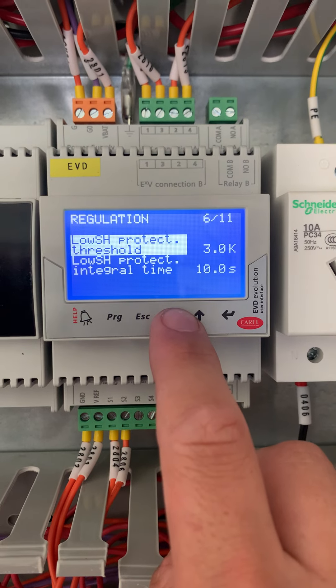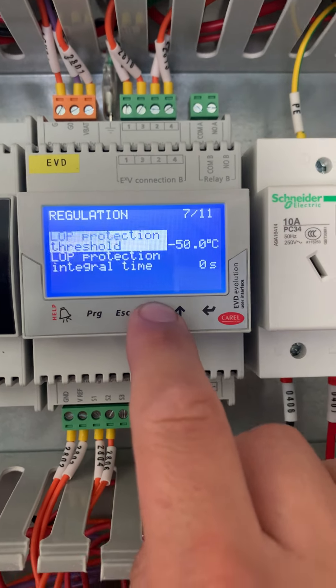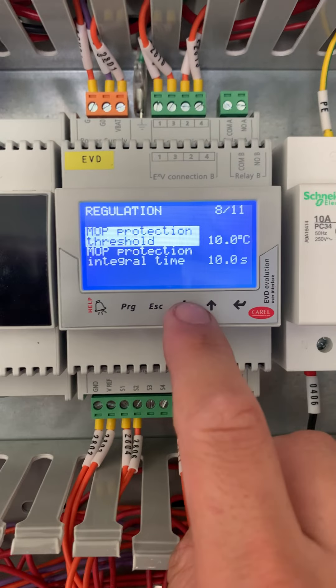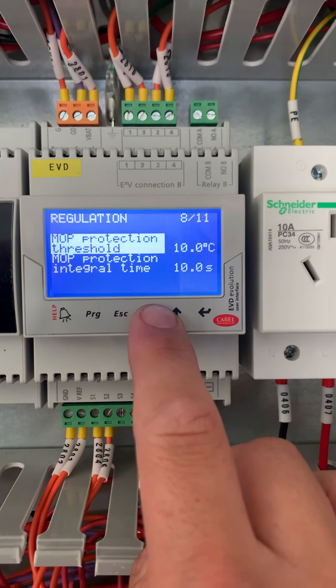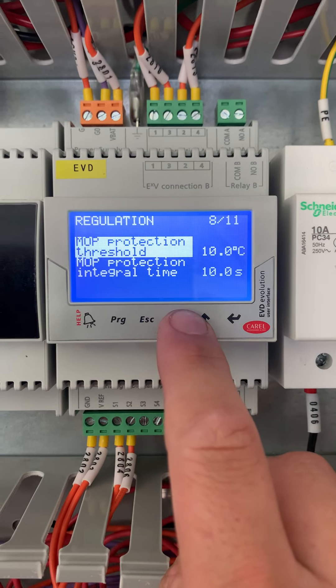Set 2 to 3K low superheat protection with a fast acting integral time. Normally set up an MOP on the freezer of about 0 to 10 degrees, again with a fast integral time for opening and closing.